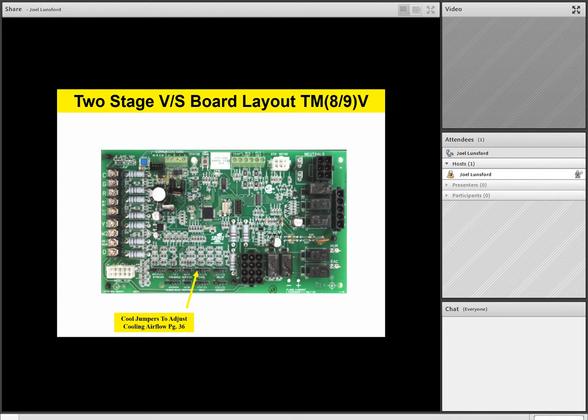Right below the cooling jumper, we have a heating jumper. And again, please refer to page number 36 in your handout or your workbook. And the heating jumpers are going to allow us to set up our heating airflow whenever we get a W call on the furnace. Any W call on the furnace will generate a heating call, and so we want to be able to set our heating airflow up based on that.